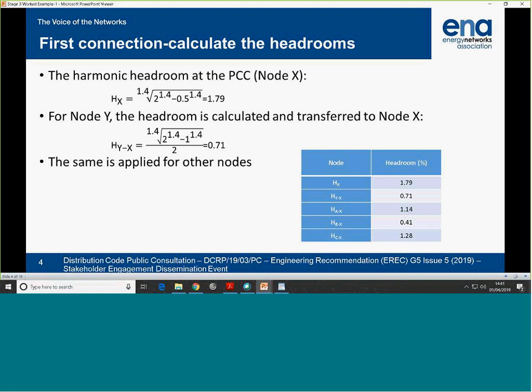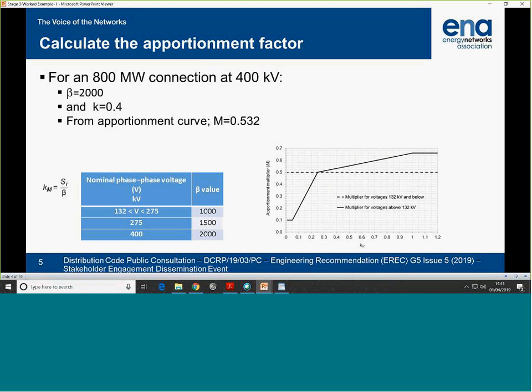Now, this applies to the same harmonic, to the other nodes, and this is the background. All buses transferred to bus bar X. Now, according to G5, I have to take the smallest. For incremental limit, I take the smallest, 0.4, which is bus bar B, my limiting node. My limiting substation is substation B. My connection is a wind farm of 800 megawatts. I take K, and for K of 0.4, my multiplier would be 0.53.